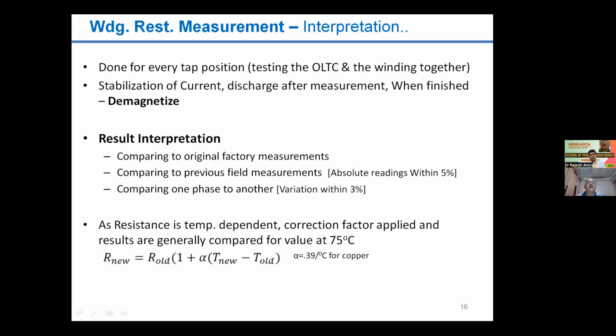During testing, the stabilization of current takes place, and after testing, the winding is demagnetized so that there is no residual magnetism inside the core. As I mentioned earlier, the winding resistance measurement is a DC test, so, of course, the residual magnetism will remain there. For this purpose, nowadays the testing kits come with an arrangement to demagnetize the core, and it is recommended that this test should be done in the last stage, when you have completed all other testing, including AC testing.